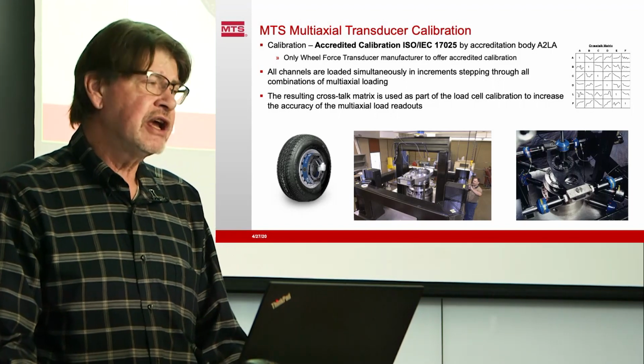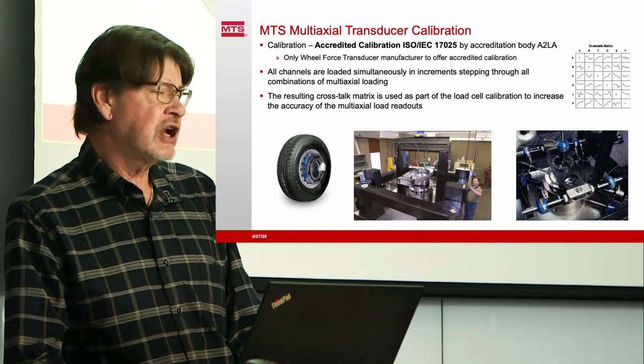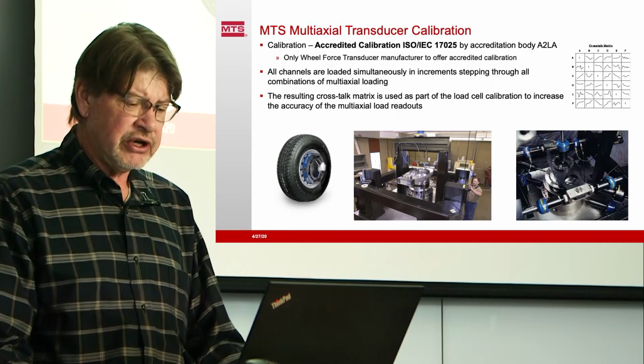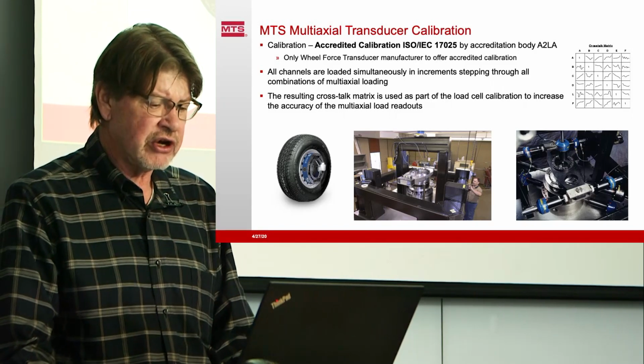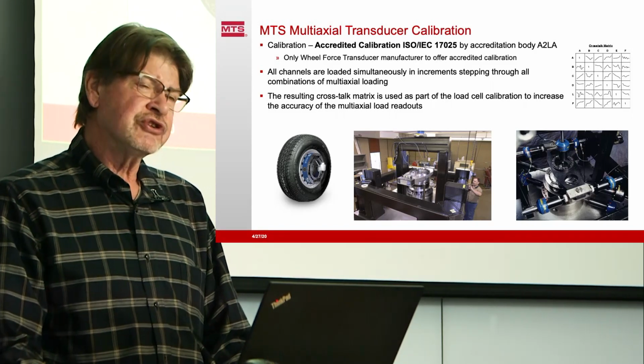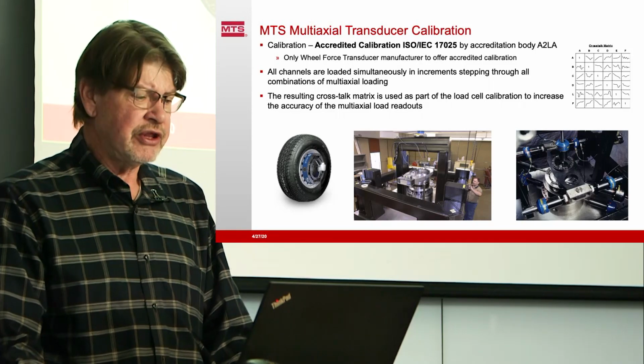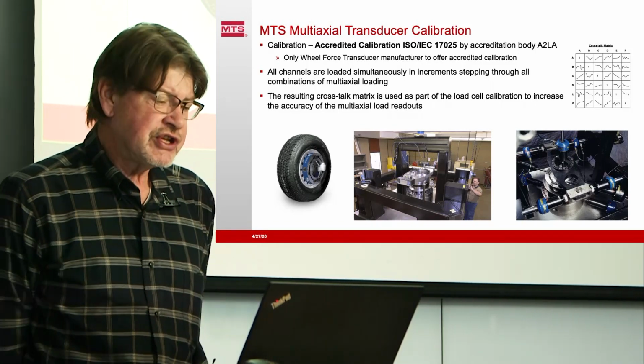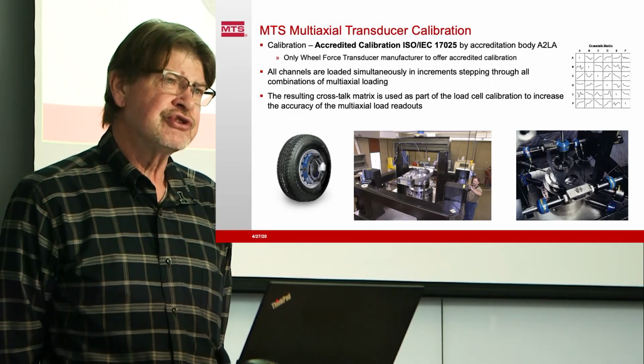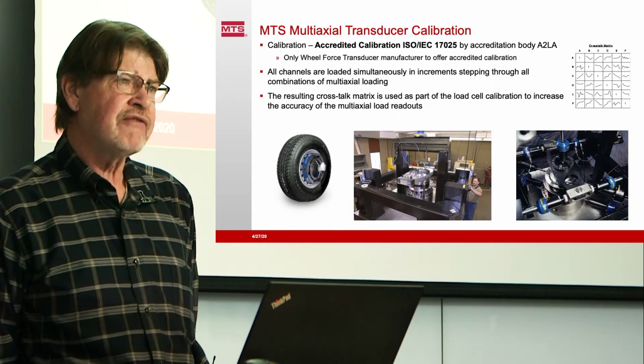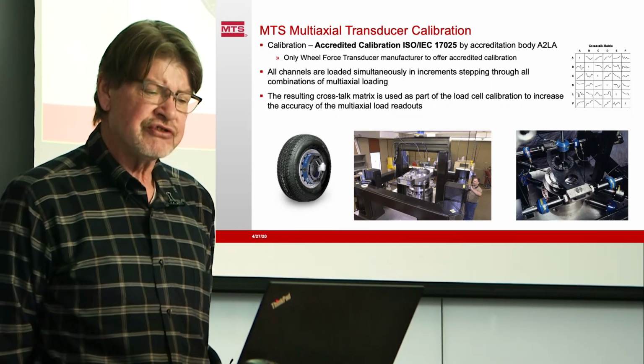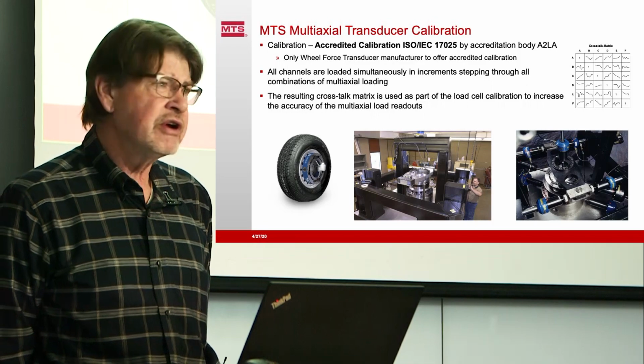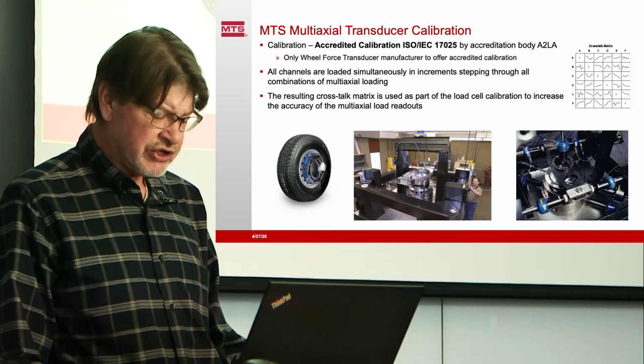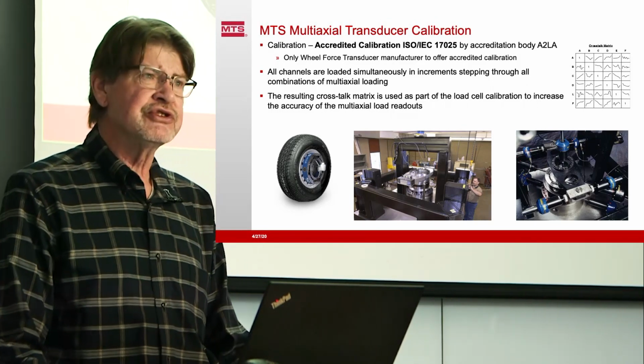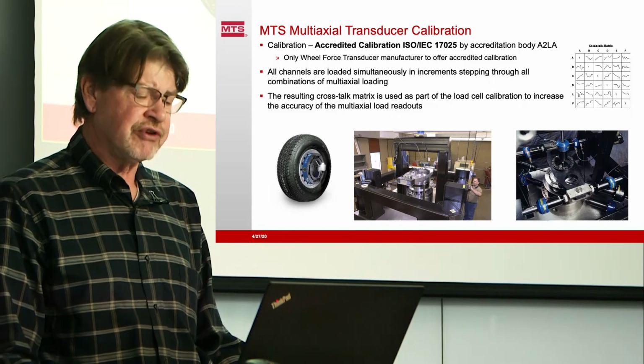MTS does a lot of multi-axial load transducers, a very complex environment that we work in here, and you can't just buy this stuff off the shelf. We're very careful with our multi-axial calibration, and one of the only companies in the world that steps the multi-axial transducer through all simultaneous combinations of load in the process of calibrating it, so we get a very comprehensive crosstalk matrix with the amplitudes and phases of all the channels across the frequency range.